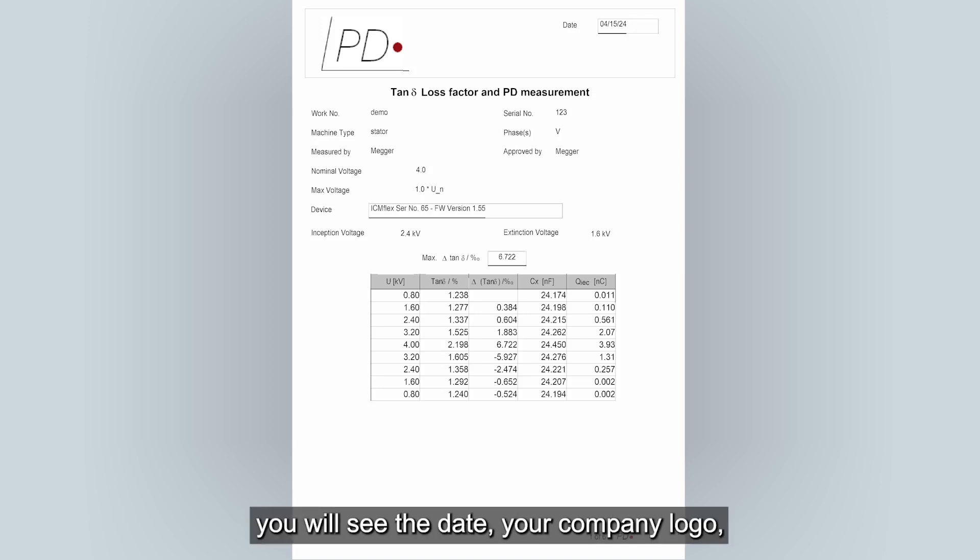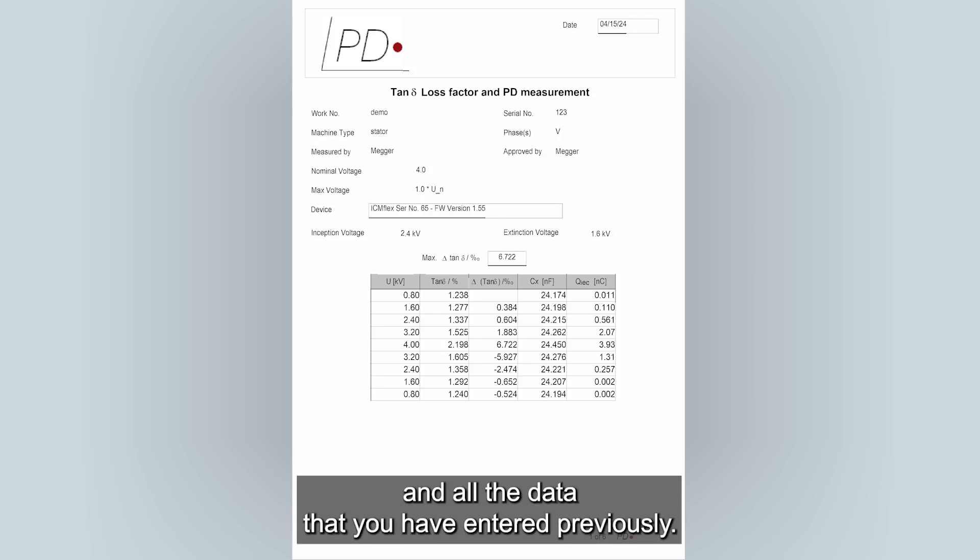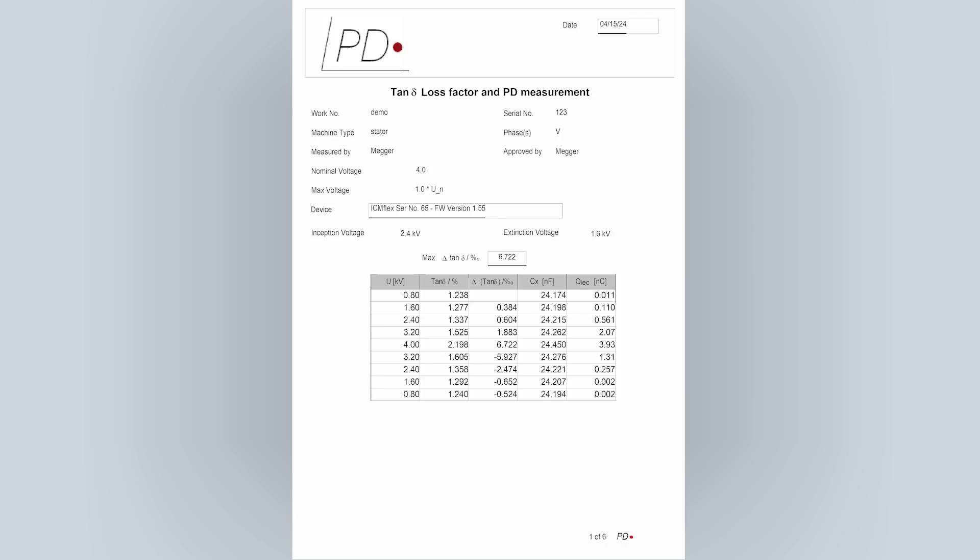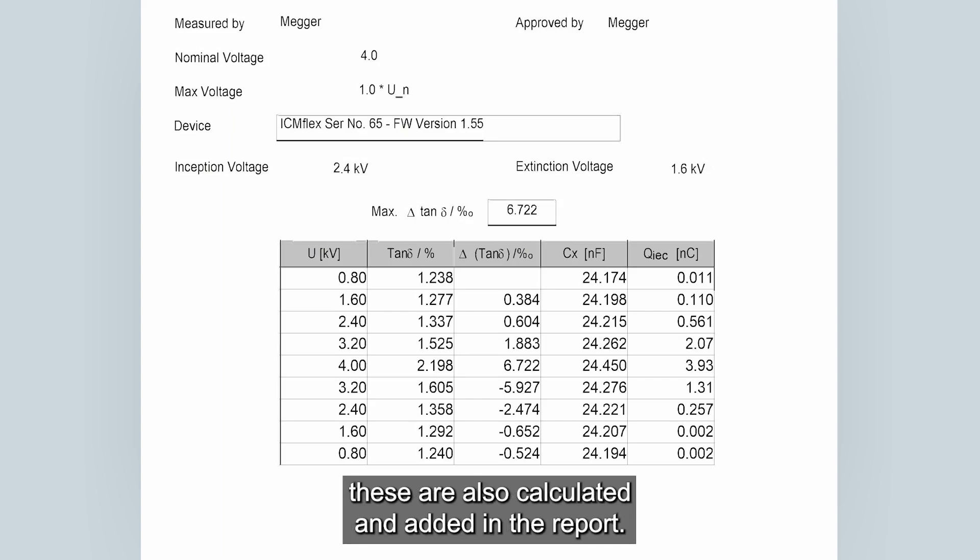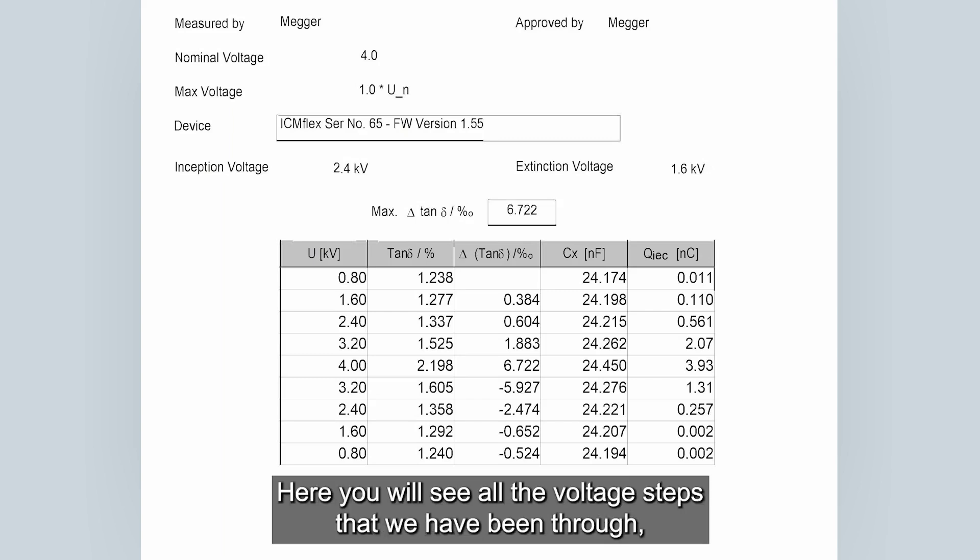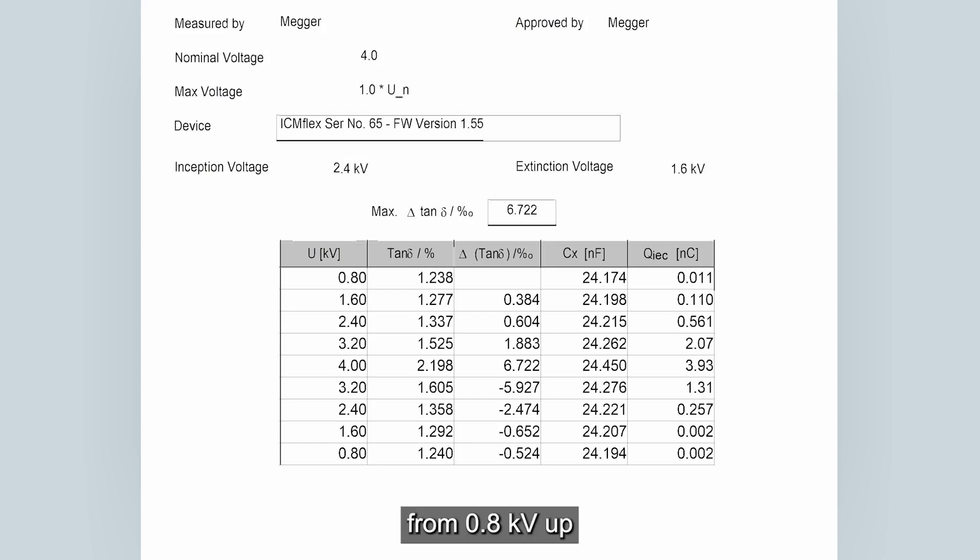The first page of the report you will see the date, your company logo and all the data that you have entered previously. Since we have chosen the options inception and extinction voltage, these are also calculated and added in the report. Here you will see all the voltage steps that we have been through. From 0.8 kV up to 4 kV and then down to 0.8 kV up and down.